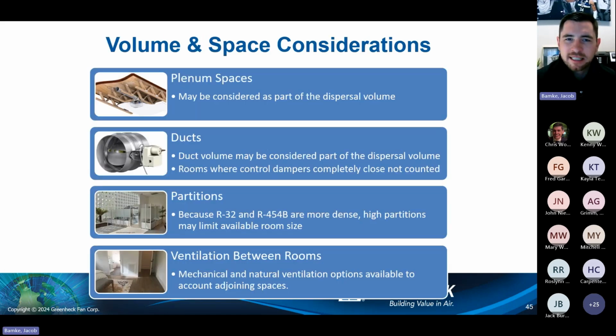So we talked a little bit about volume and space requirements. What are some considerations to think about? First is plenum spaces. Plenum spaces may be considered as part of the dispersal volume. So it's not just the space itself, but you can also look at the plenum requirements. Ducts: duct volume may be considered part of the dispersal volume as well. Rooms where control dampers completely close cannot be counted. Partitions: because these A2L or R32 and 454B refrigerants are more dense, they tend to settle at the bottom of the space. So depending on how high the partition is, it may limit the available room size that you can use as part of the distribution space area.